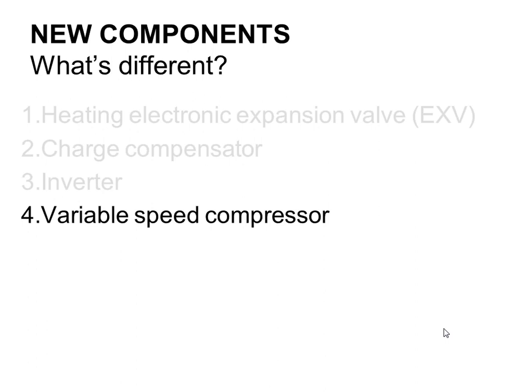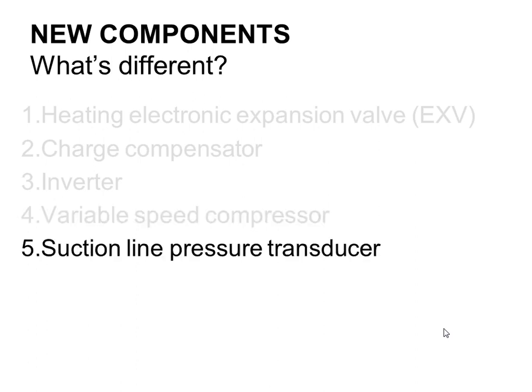The compressor is actually a DC compressor, right? Whereas most compressors we use are AC, alternating current. This is DC, and the reason for that is an inverter, like a VFD, every time you convert power from AC to DC and back again, it wastes some energy, which is basically heat, right? Put your hand on a VFD cabinet, it's always hot. It's wasting energy that way. If we have a DC compressor, it's one less conversion point, so one less waste of energy, if you will.